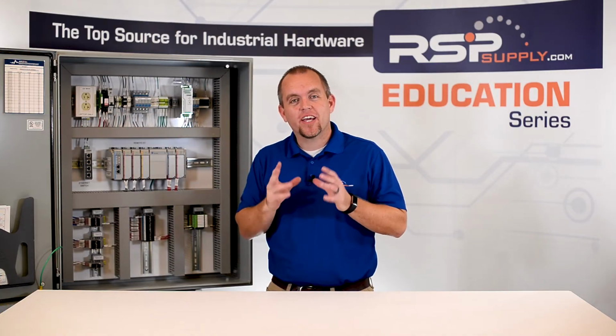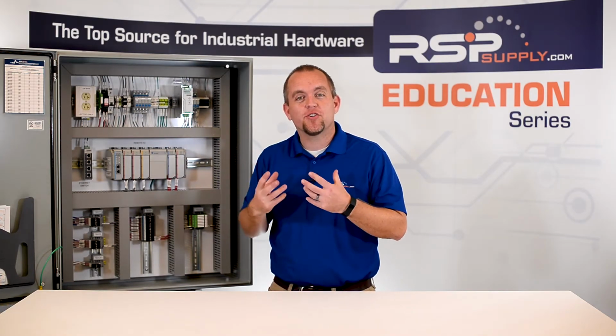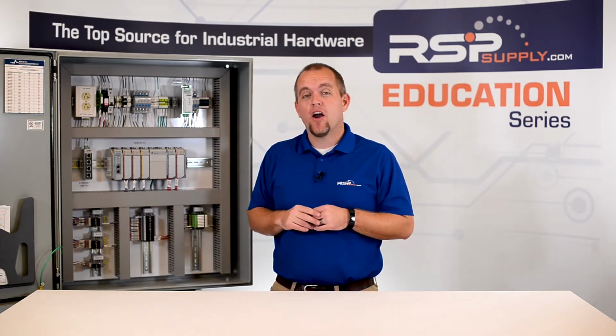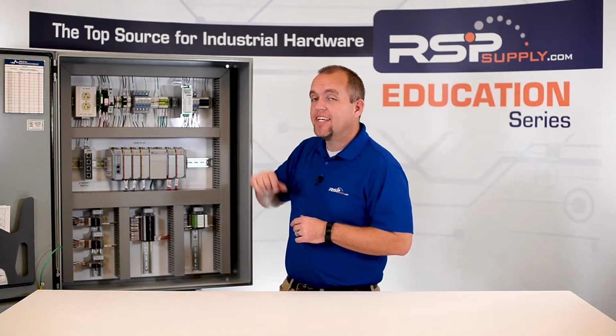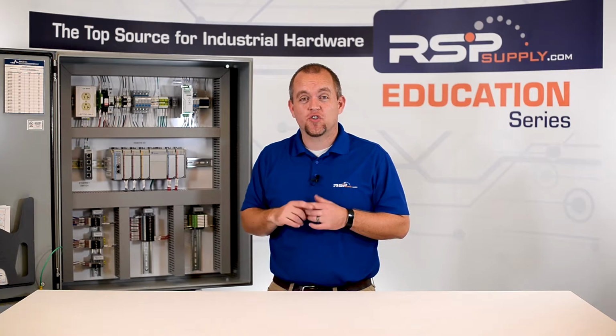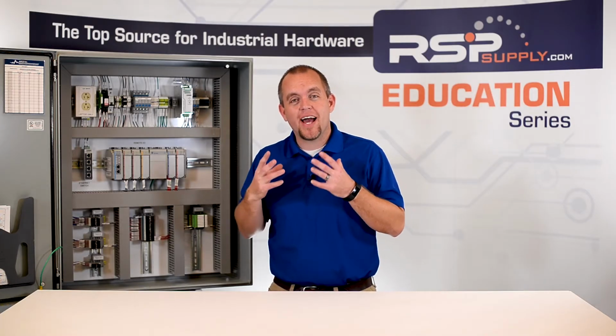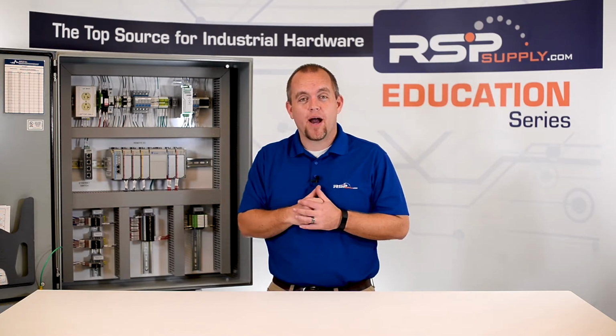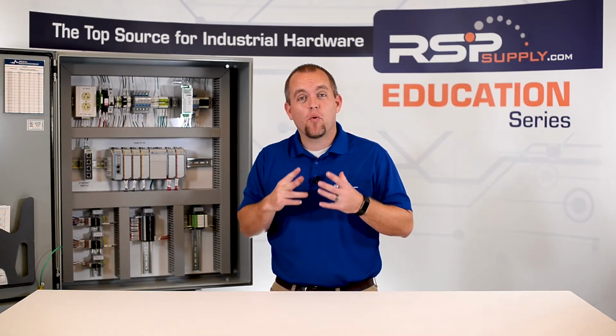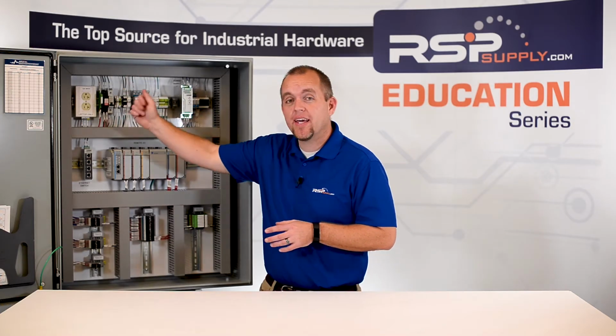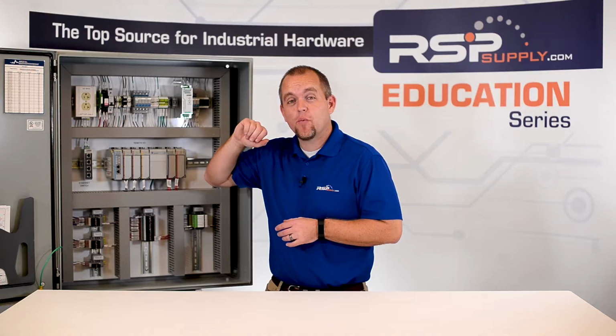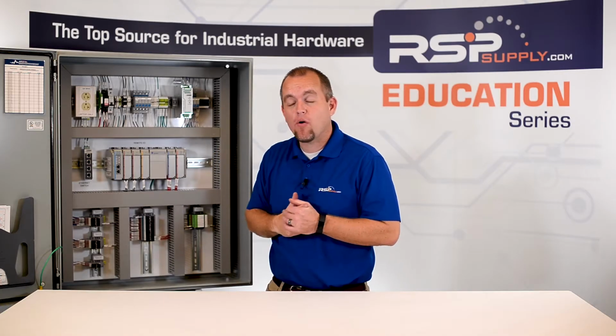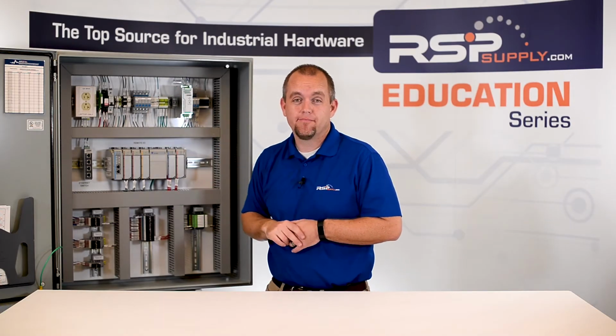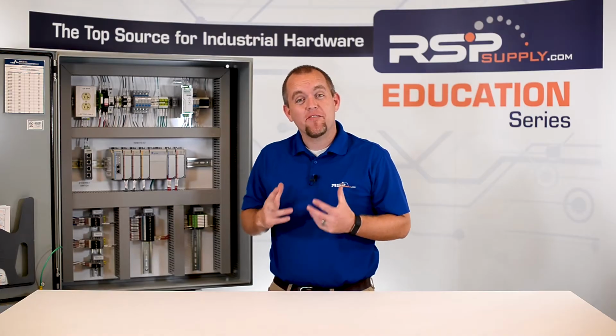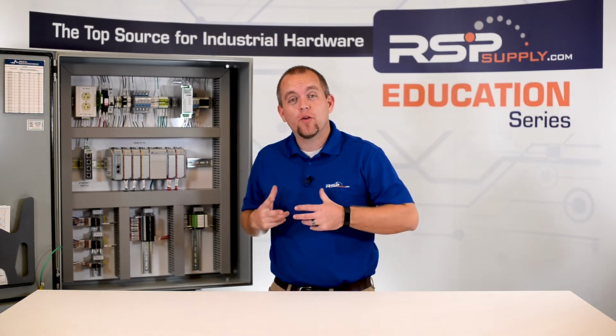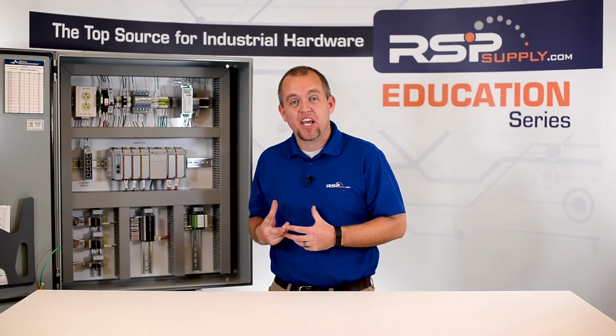We want to consider again where that power is going to be entering the panel itself. Typically, our main power distribution is going to be on the top of the industrial control panel. This is where people tend to naturally look to disconnect power to the panel. It is also important to make sure that any power coming in is properly labeled so that we can easily identify the type of power and where it's being terminated. So again, referencing the type of power that we have coming into our panel, we need to make sure that we have a very good understanding of that power.